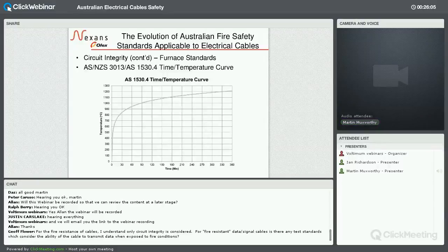So there's a fairly obvious conclusion that can be derived from this particular curve, and that is that copper conductors, for example, is the only type of material or metal commonly available in the cable industry that can survive this test, because it's got a melting point about 1,083.